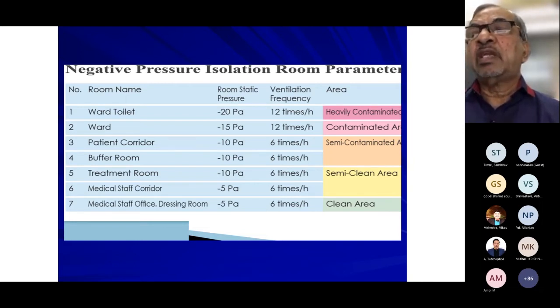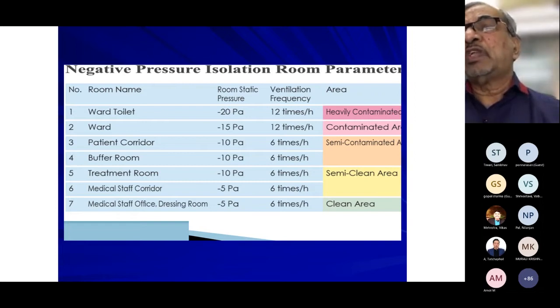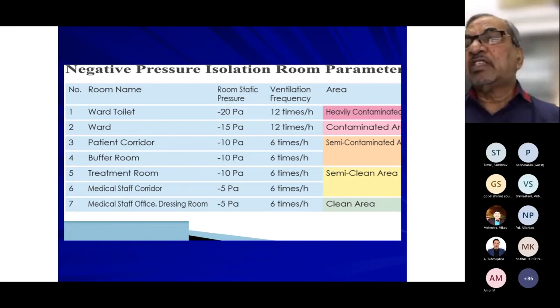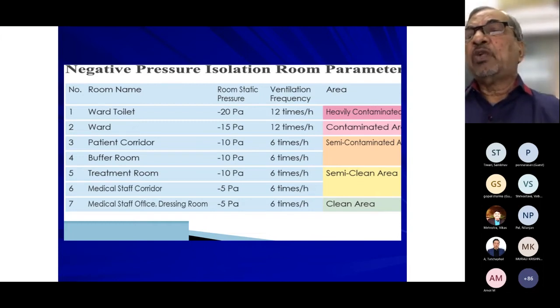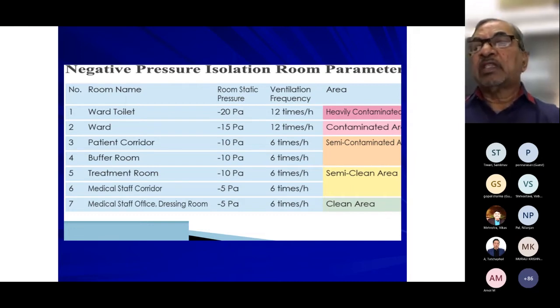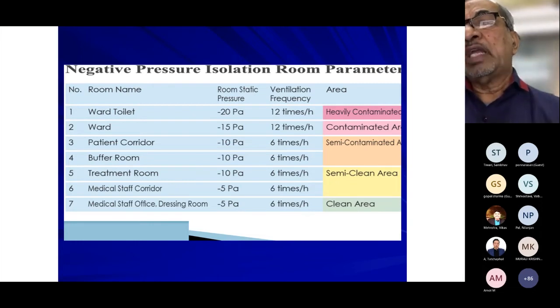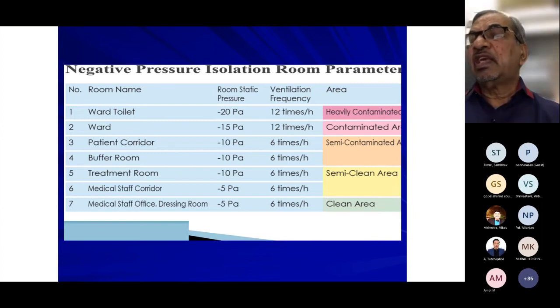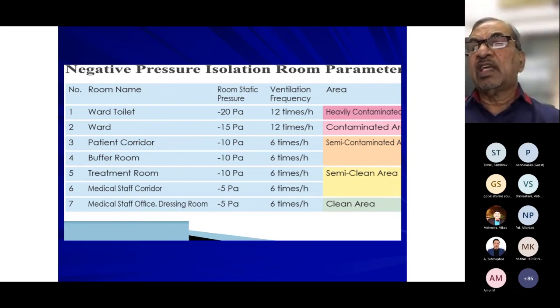The ward is next, at minus 15 pascal, and the patient corridor is minus 10, with 6 air changes per hour. The buffer room is minus 10 pascal, the treatment room is also minus 10 pascal, and generally the medical staff corridor, medical staff office, and dressing room are kept at minus 5 pascal, because there they use a lot of protective methods with standard operating procedures.